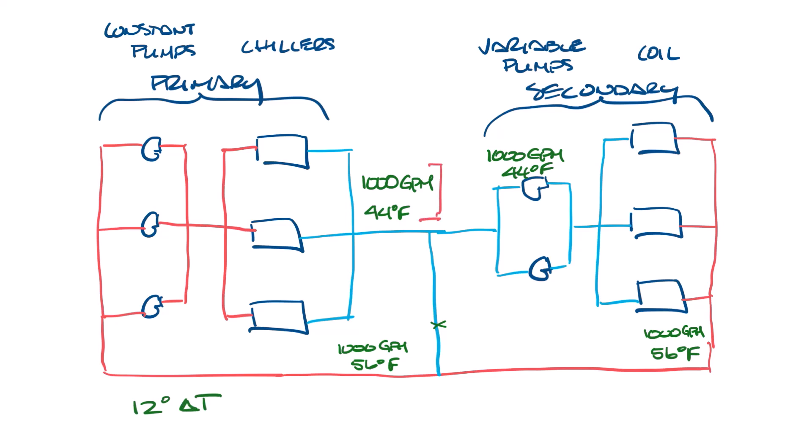Now let's say we still have that thousand GPM and 44 degree water here, but to make the math easy, let's say the secondary pumps are only moving 50% of the supply water. So the other half would be diverted through the decoupler. So at this point you'd have 500 GPM and 44 degree water coming through the secondary pumps and to the water coils. And so we'll have 500 GPM and 56 degree water coming out of the coils. Since 500 GPM were diverted to the decoupler, that water is going to mix with the water coming out of the coils and you're going to end up with a thousand GPM and 50 degree water over here going back to the return side of the chillers. And so that's a six degree delta T.